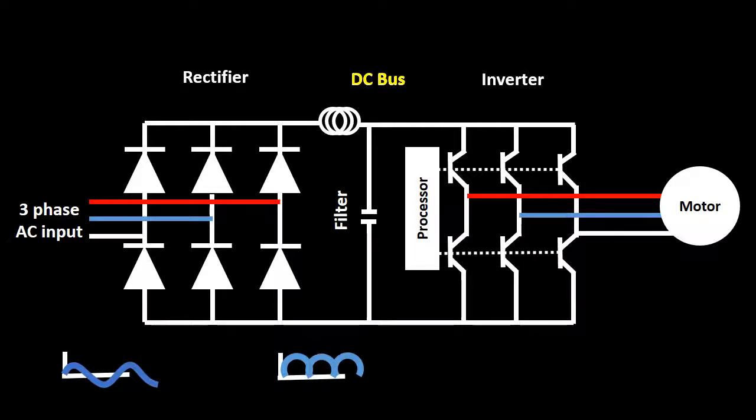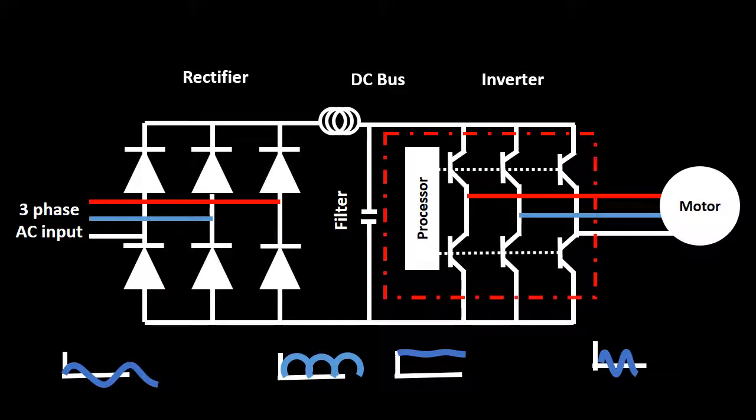We will now look at how a VSD achieves its variable output frequency. The construction of a VSD can be divided into three main sections: the rectifier, the DC bus, and the inverter. The AC input firstly passes through the rectifier onto the DC bus, which supplies the inverter DC input. The inverter then converts the DC back into AC at the chosen frequency. This is done by applying a switching pattern on the DC bus to approximate a sinusoidal output of the desired frequency.